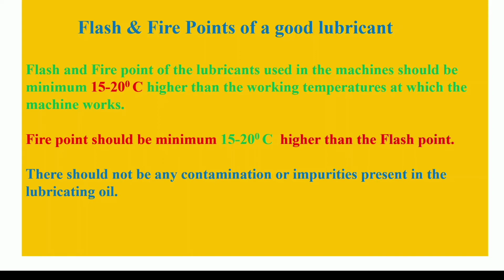Therefore, for a good lubricant, the flash and fire point of it should be minimum 15 to 20 degrees centigrade higher than the working temperatures at which the machine works.